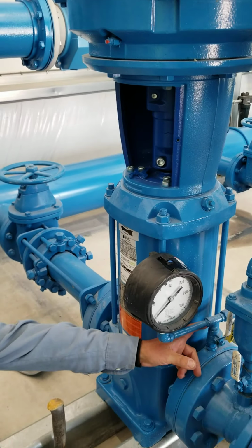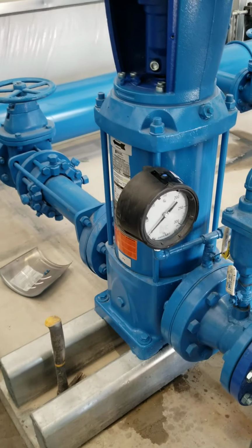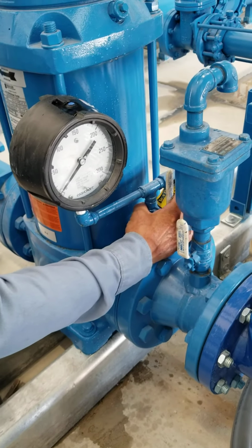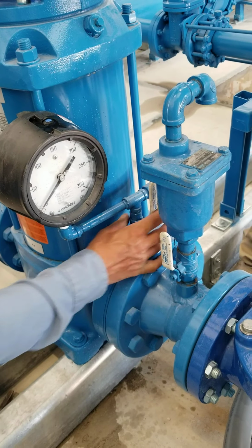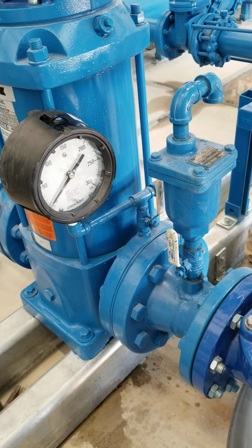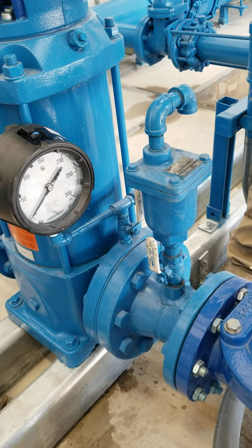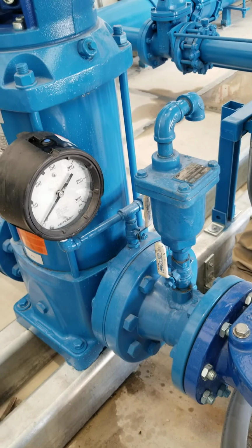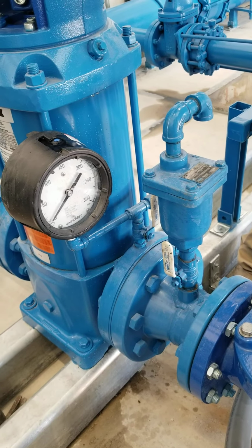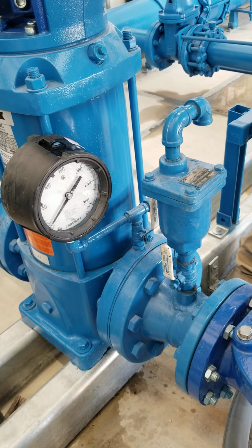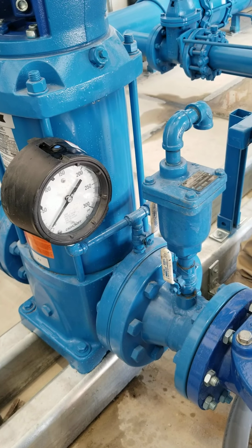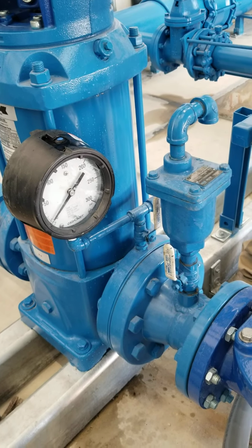Did you talk about the purge valves too? No, Mark, go ahead. These are temperature rated purge valves. So if somebody deadheads the pump and the pump starts to get hot, that's going to pop off. Okay. So if you ever see them dripping, it could be going bad. It could have debris in it. And I don't know if they're rebuildable. They're cheap enough, you can just replace them.